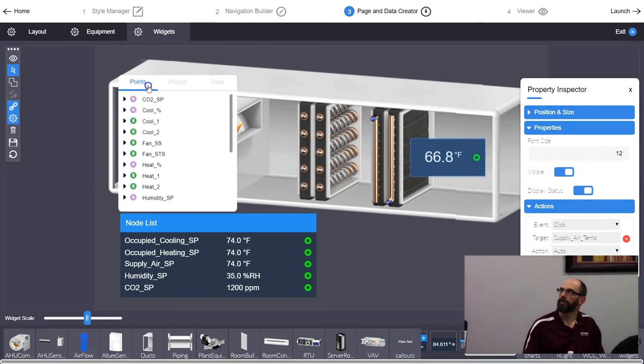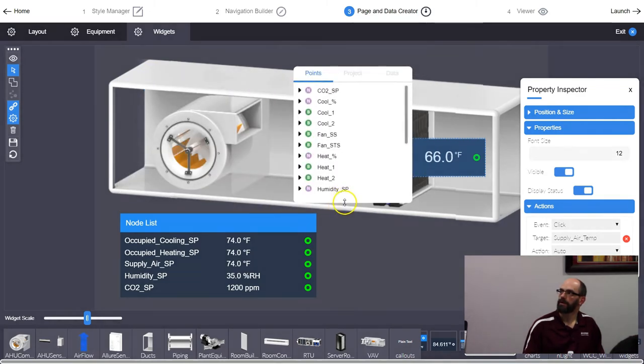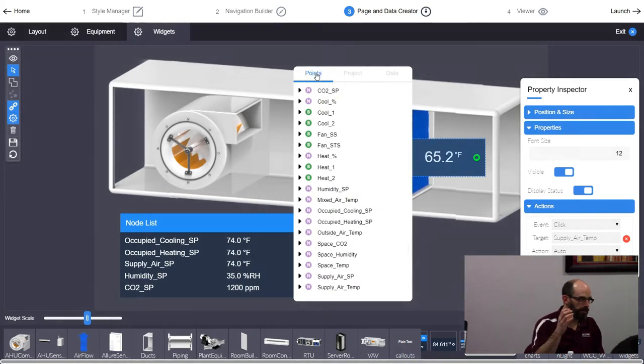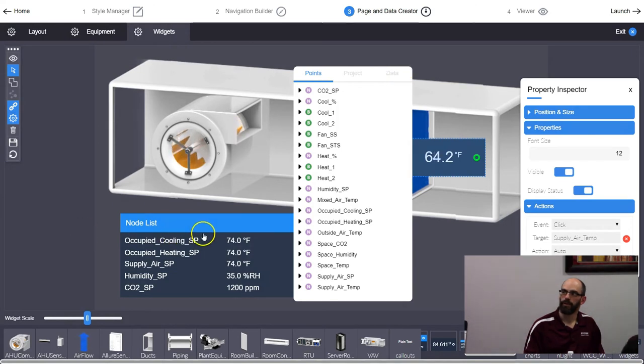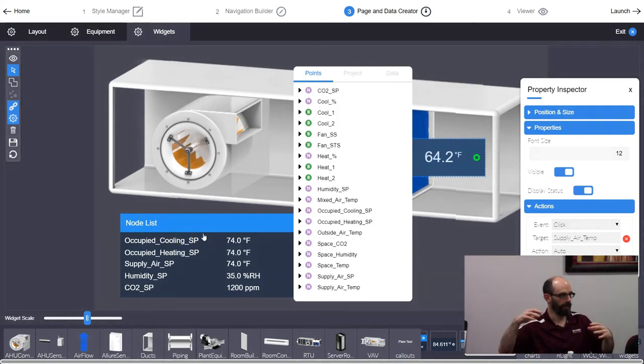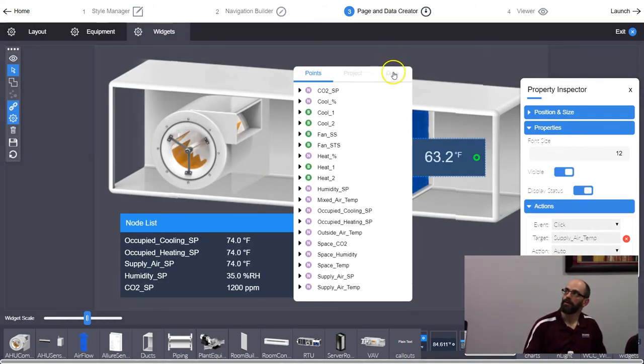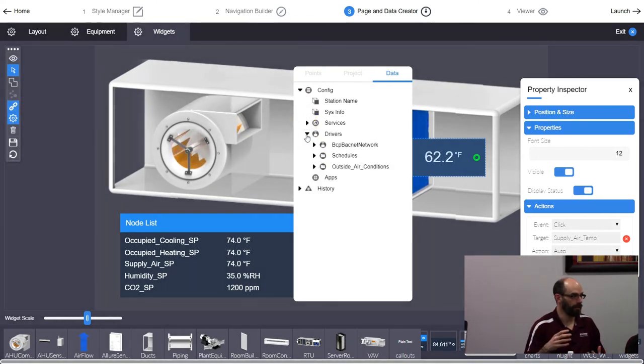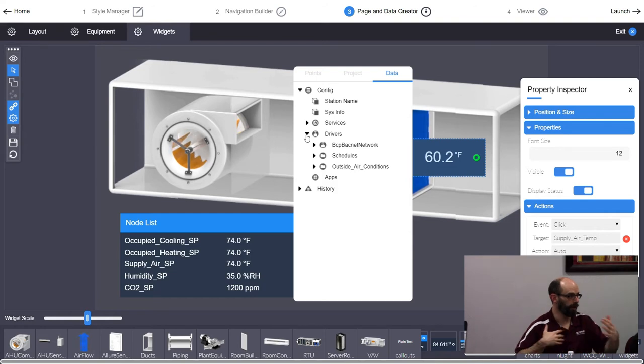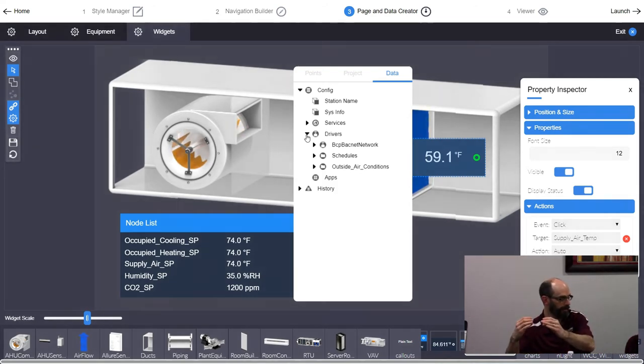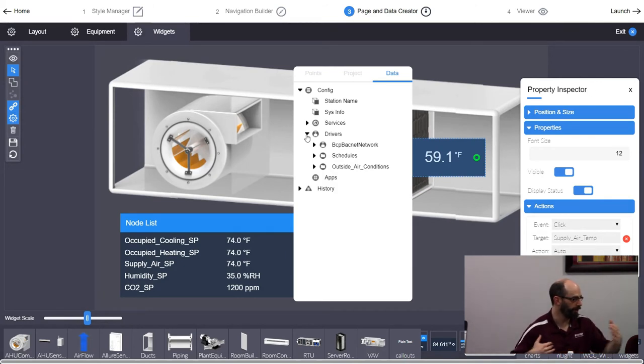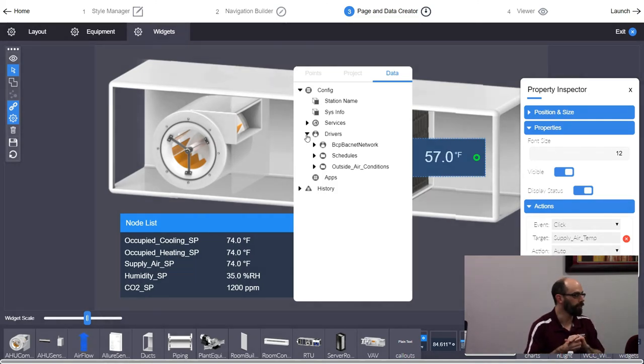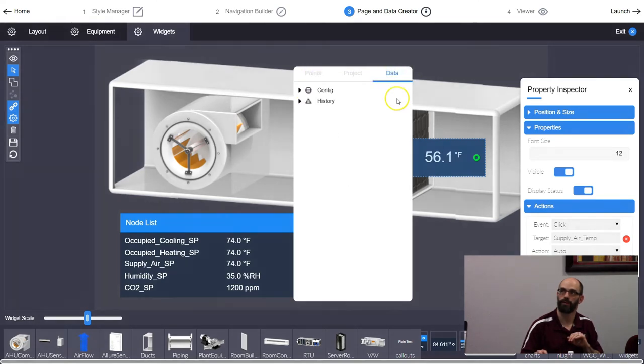Here's an important concept: when pulling points from the key controller's list, those values update to whatever controller you're currently looking at — they relativize. If you link a point from the data tree instead, it's a static link. No matter what graphic you're viewing, it'll always show the same value. So if I'm showing air handler supply temp on all my VAVs and I pull it from the data tree, it'll always show that one specific supply temp — it will never update to each individual VAV.